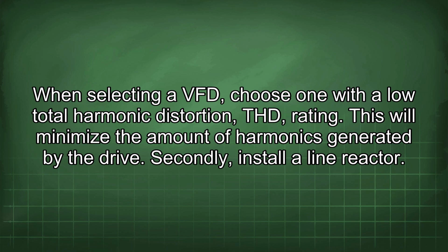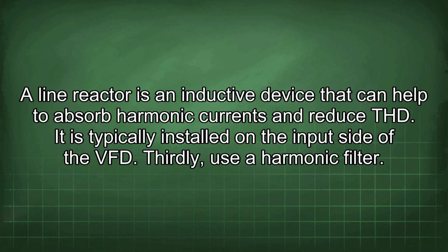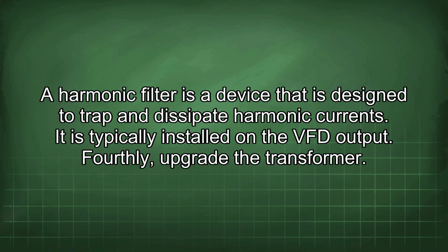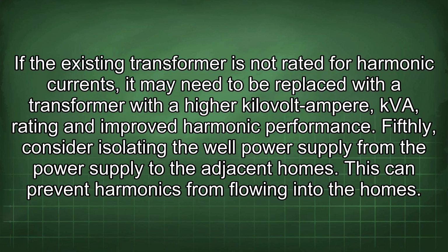Secondly, install a line reactor. A line reactor is an inductive device that can help to absorb harmonic currents and reduce THD. It is typically installed on the input side of the VFD. Thirdly, use a harmonic filter. A harmonic filter is a device that is designed to trap and dissipate harmonic currents. It is typically installed on the VFD output. Fourthly, upgrade the transformer. If the existing transformer is not rated for harmonic currents, it may need to be replaced with a transformer with a higher kilovolt ampere (kVA) rating and improved harmonic performance. Fifthly, consider isolating the well power supply from the power supply to the adjacent homes. This can prevent harmonics from flowing into the homes.